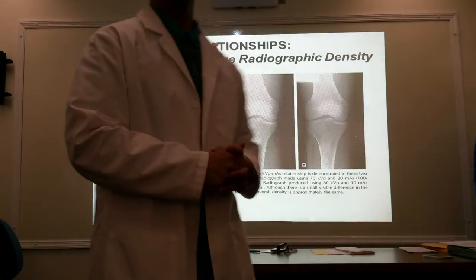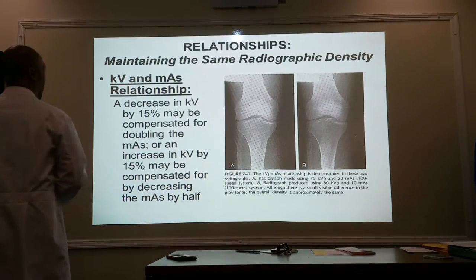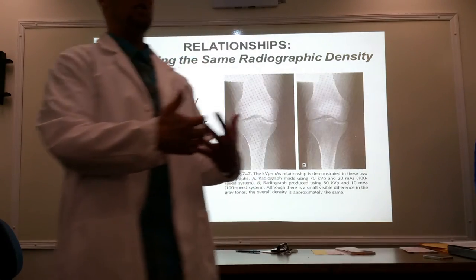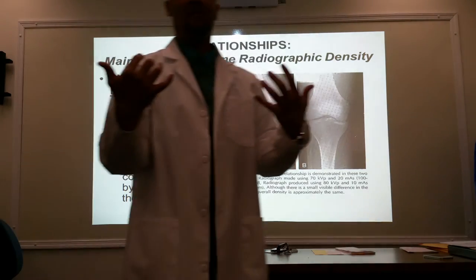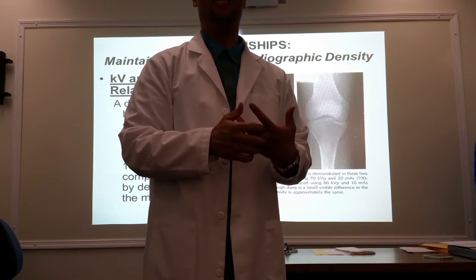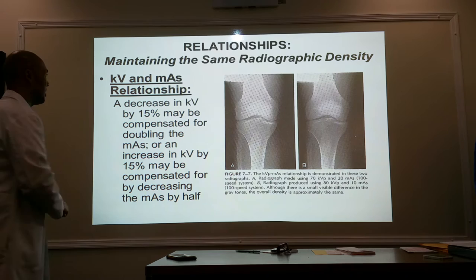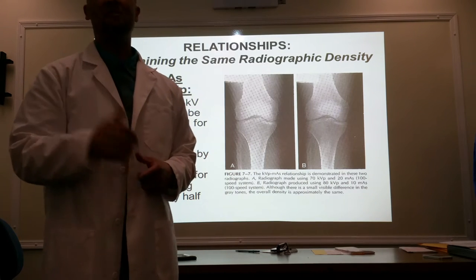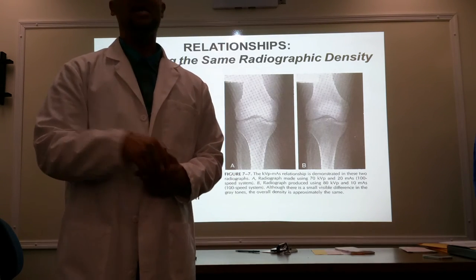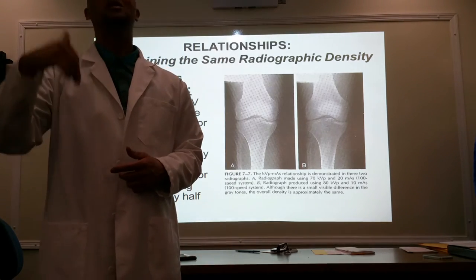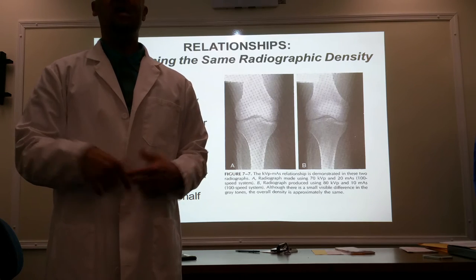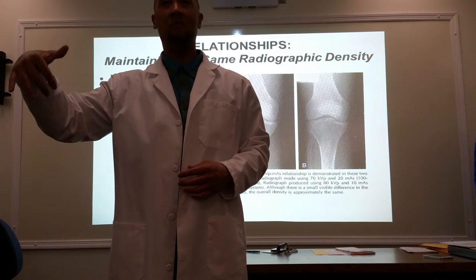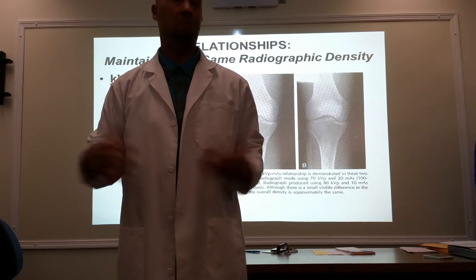Now we need to take our tools and learn how to work with them as a whole. We're going to be talking about the KV and MAS relationship and its effect on overall density. We already know that if you increase or decrease your KV by 15%, you're doubling your density or cutting it in half. The same goes with MAS — if you double it or cut it in half, you're also doubling or cutting your density in half.